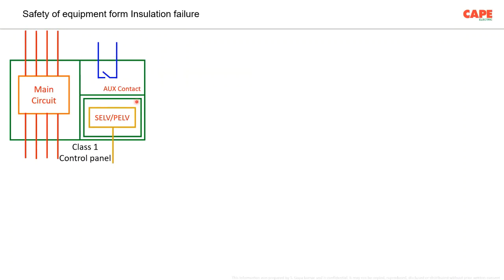Now, if you have a control panel in this fashion, what we should ensure is between the main circuit and the auxiliary circuit, SELV, PELV, number one, there must be a physical insulation, physical separation. The auxiliary and this particular SELV and PELV must be installed within the double insulated part of the installation. It means that mechanically, the SELV and PELV circuit must be insulated. This also means in case of a problem on the main circuit, a person who is working on the SELV, PELV or on the auxiliary circuit is not getting electrocuted.